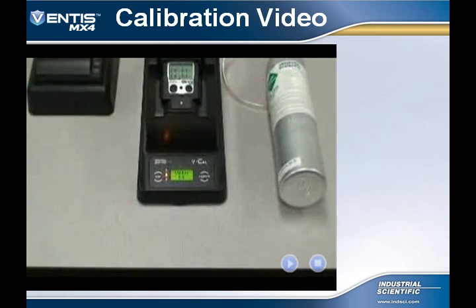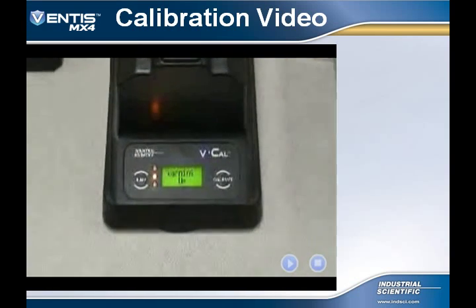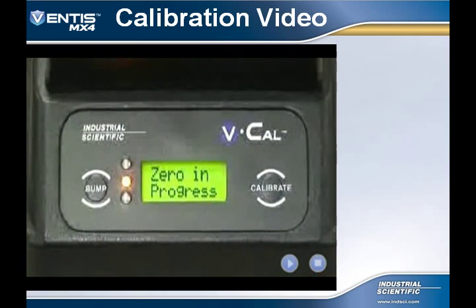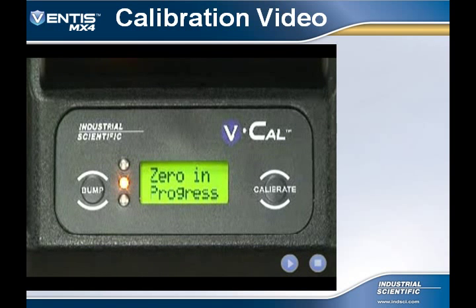After the warm-up, the VCal will zero the instrument. Zero in progress will be displayed on the screen. After the zeroing process, cal in progress will be displayed on the VCal screen. At this time, all sensors are being calibrated simultaneously.